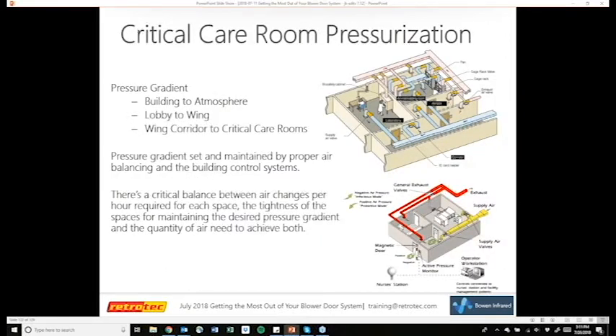Critical care rooms and medical facilities such as hospitals. So this is really important, especially if you have like quarantine areas, or if you need to put a negative air pressure, that would be like infectious mode, or positive air pressure, which would be protective mode, to really separate two areas out. You would use a blower door to test different rooms to make sure that they're going to be separated from others, and to see how those airflow patterns in the duct system are going to behave. So that's another place where blower doors are used, in hospitals.